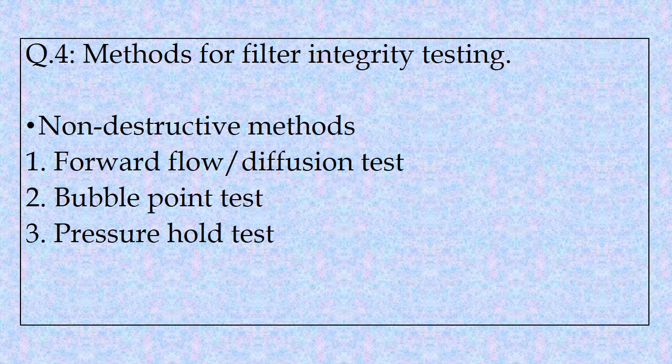Question 4: What are the methods for filter integrity testing? Most commonly, non-destructive methods for filter integrity testing are deployed, which include: first, forward flow or diffusion test; second, bubble point test; and third, pressure hold test.